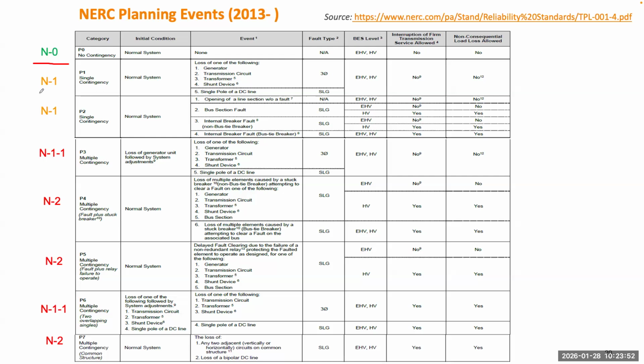Starting from the second one, you will see N-1, which means you lose a single element. But the system still needs to be safe and meet all the standards, like voltage, frequency, synchronous generators, and also the integrity of the grid. And this one, P3, is called N-1-1. It studies a base condition which is already N-1, and then you lose one additional element. So this one could be one of the conditions from maybe the second or third category, before you fix this problem, and another contingency happens, so you lose one more element. And there's also a category where you lose two elements together at the same time, starting from N-0. From N-0, you lose two elements, so that will be N-2. Yes, this is also N-2.